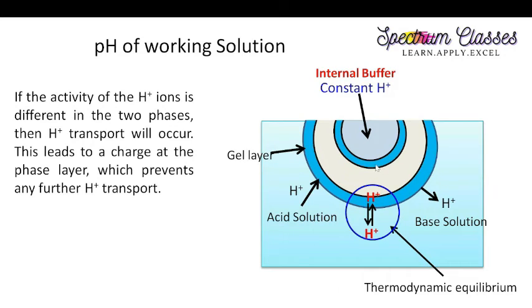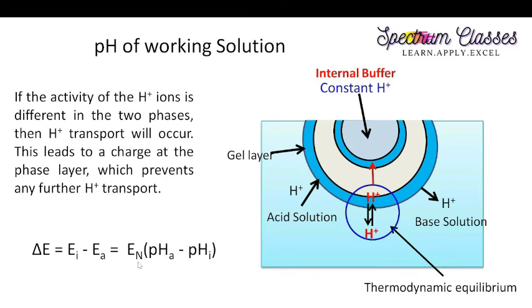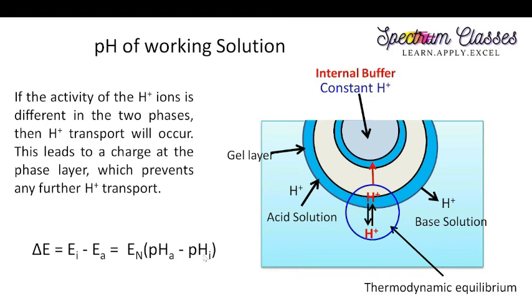When this signal is transmitted, the difference between the activity of the internal buffer and the working solution is measured through the equation: ΔE equals E_internal minus E_acid solution, which equals EN (the slope factor) times (pHA minus pHI). This difference in pH values between the internal and working solutions is measured as a potential, and this potential is further converted to the pH of the solution.